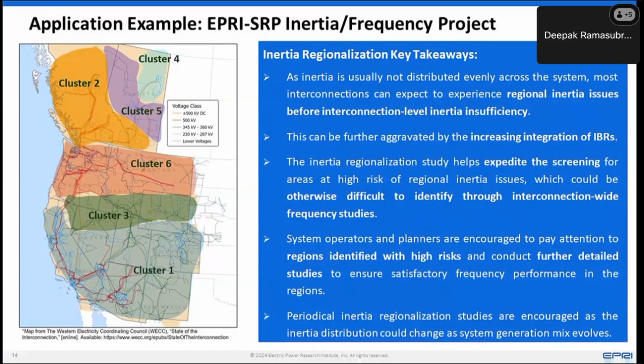So it does not take into account fast frequency response. The way to think about it: inertia clustering right now is looking at how rotational inertia is decreasing in your system. Fast frequency response is sort of a remedy to rotational inertia. So as you transition from an all-synchronous machine system to one with inverter-based resources, where you may or may not have the provision to provide fast frequency response, this type of tool allows you to identify clusters where you really want to start thinking, I need to put in fast frequency response. That's the approach we've taken to identifying this regional inertia risk.